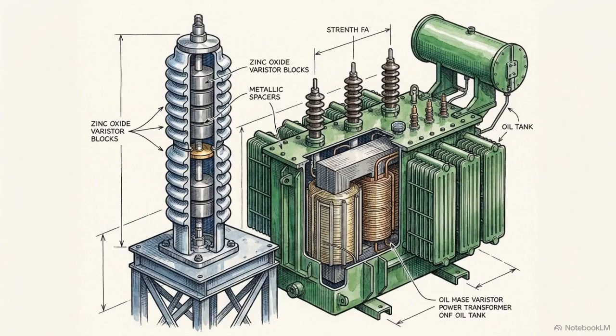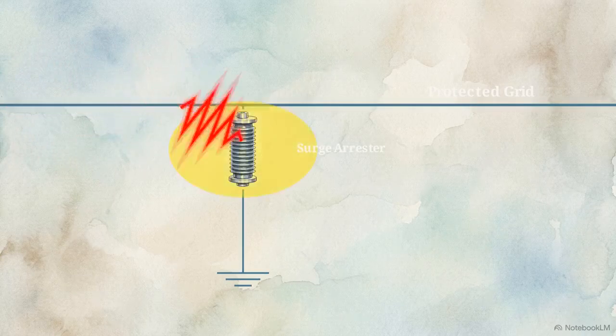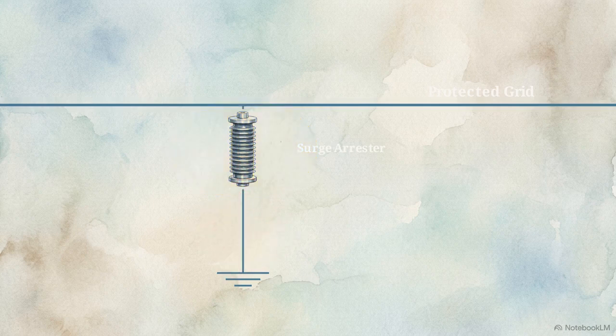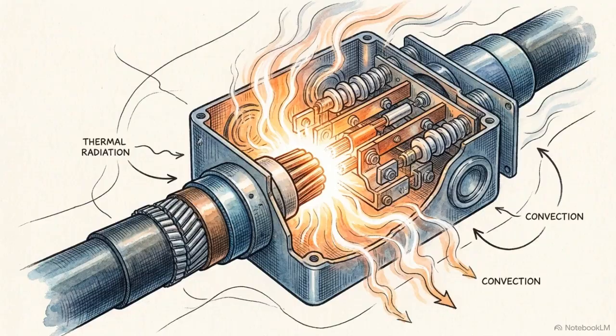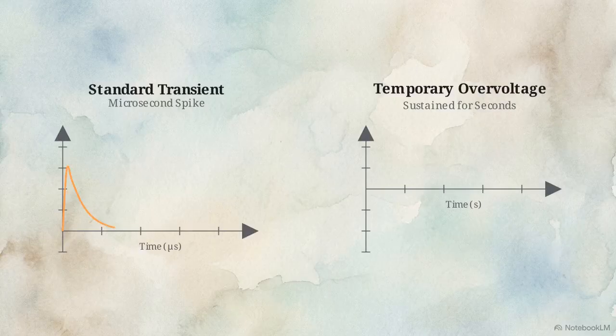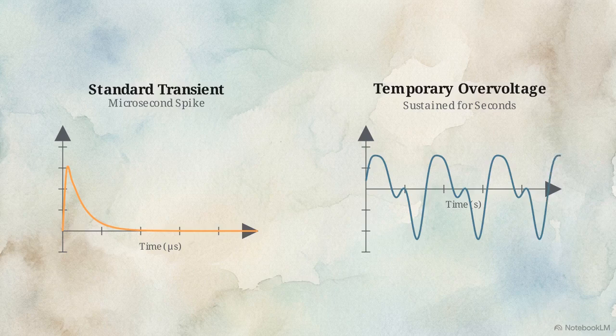When transformers are under threat, grid operators rely on an ultimate shield to protect the equipment: the metal oxide surge arrestor. Under normal conditions, an arrestor works by briefly clamping down on fast, microsecond-long voltage spikes, safely bleeding the excess energy into the ground. But the exact same cable switching events that cause high-frequency shockwaves also give birth to a secondary threat: temporary overvoltages, or TOVs. This timeline illustrates the difference. A standard transient is a sharp microsecond spike, while a temporary overvoltage is a rolling harmonic resonance sustaining for seconds.